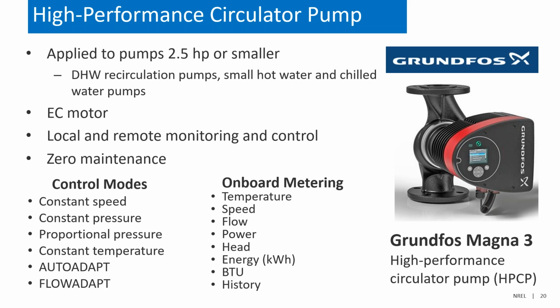I think one thing to note here is that the Energy Policy Act of 1992, which set some of the first motor efficiency standards in the U.S., only goes down to 1 horsepower. So a lot of times when you're looking at these really small pumps, they tend to have much lower motor efficiencies and power factors than some of the larger induction motors. And really the technology innovation here comes from moving from an induction motor to an ECM motor. It has integrated variable speed control, so you don't have to have a secondary variable frequency drive.